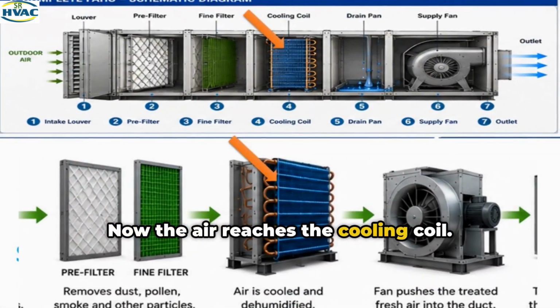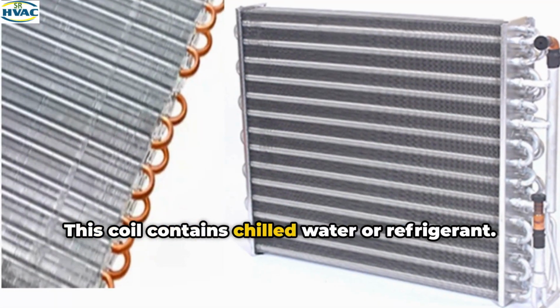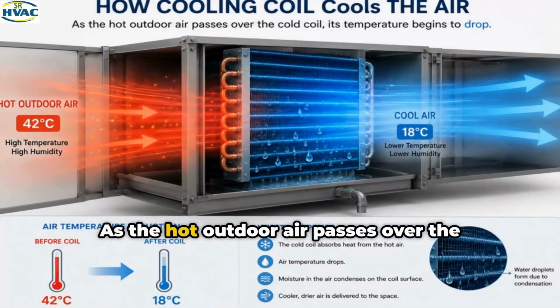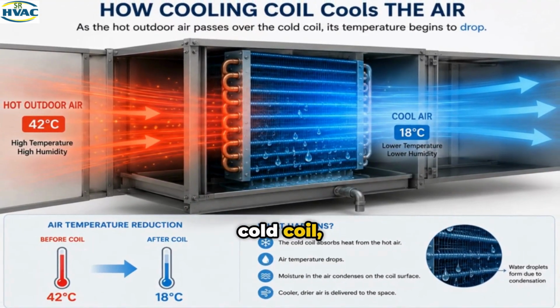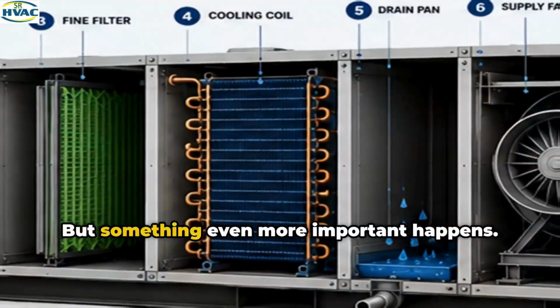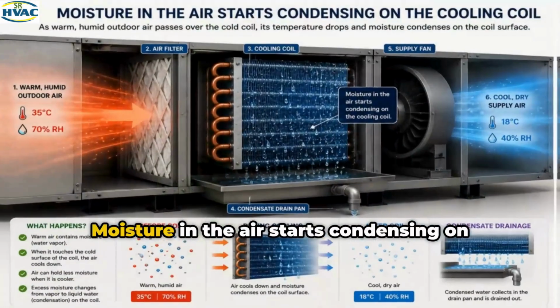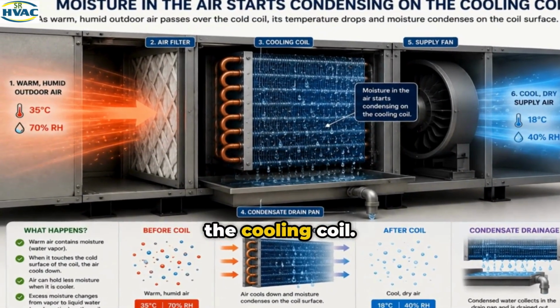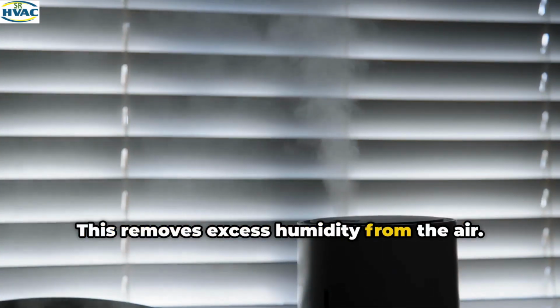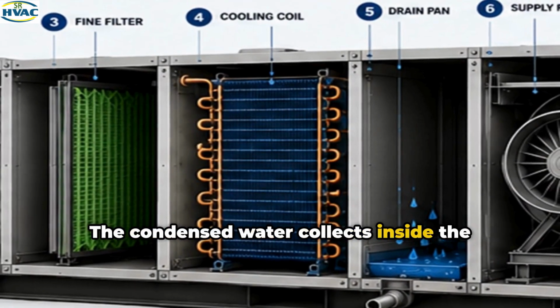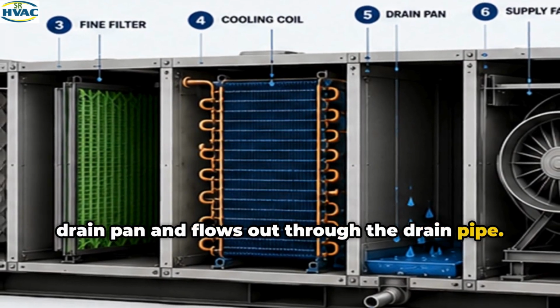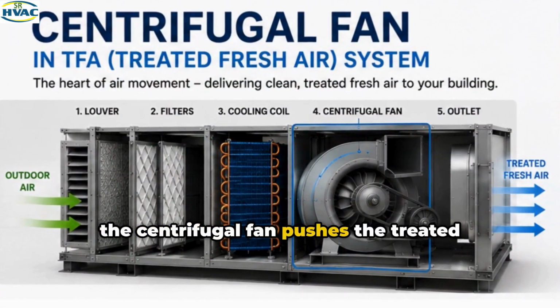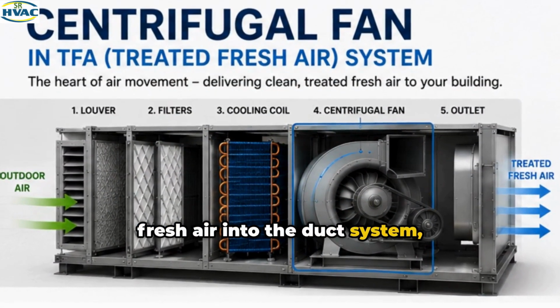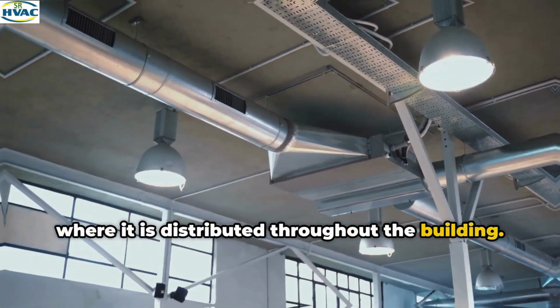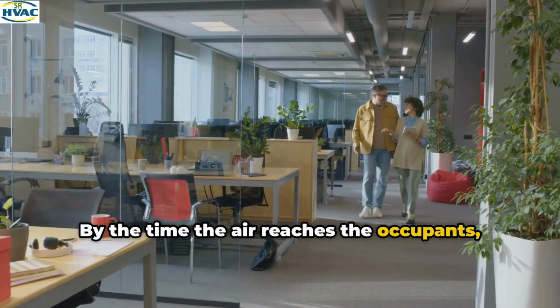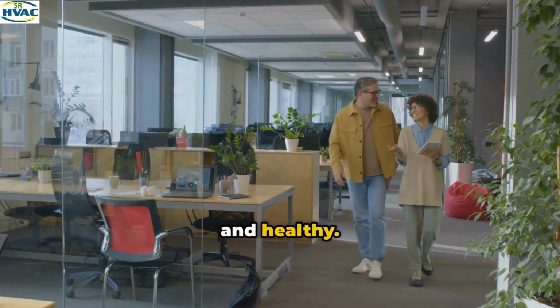Now the air reaches the cooling coil. This coil contains chilled water or refrigerant. As the hot outdoor air passes over the cold coil, its temperature begins to drop. But something even more important happens. Moisture in the air starts condensing on the cooling coil. This removes excess humidity from the air. The condensed water collects inside the drain pan and flows out through the drain pipe. Finally, the centrifugal fan pushes the treated fresh air into the duct system where it is distributed throughout the building. By the time the air reaches the occupants, it is clean, cool, comfortable and healthy.